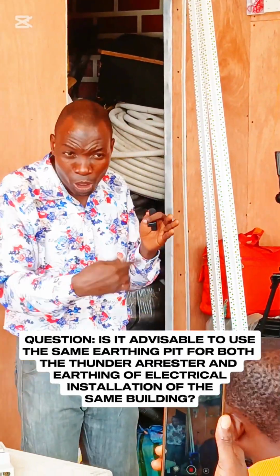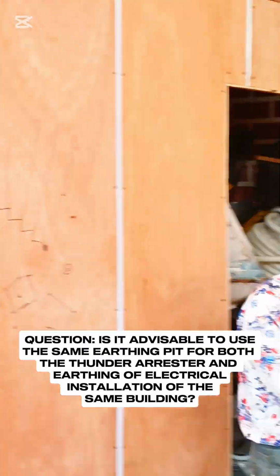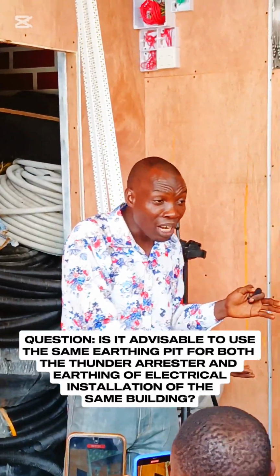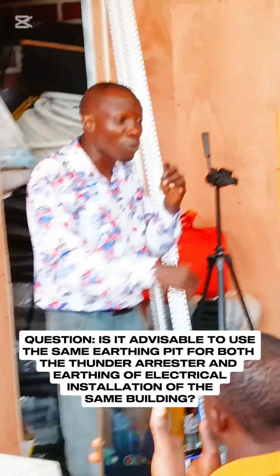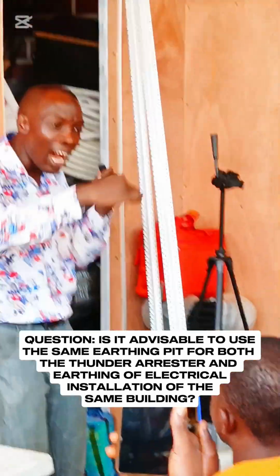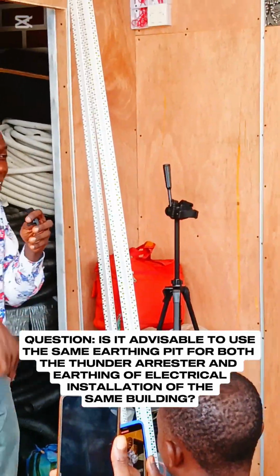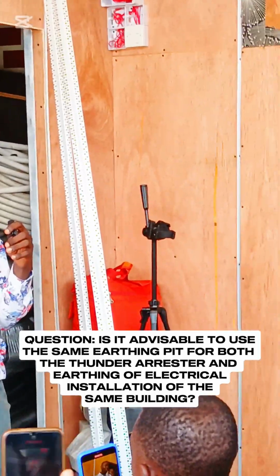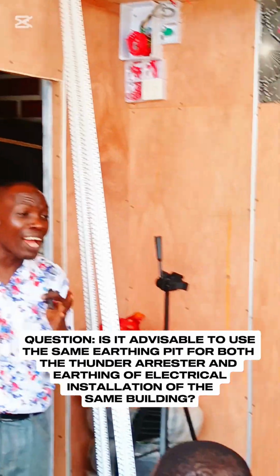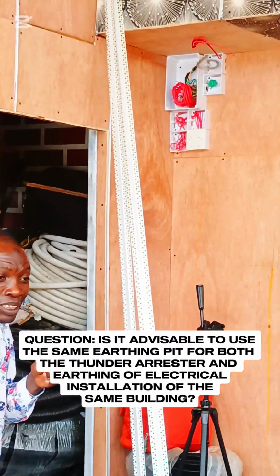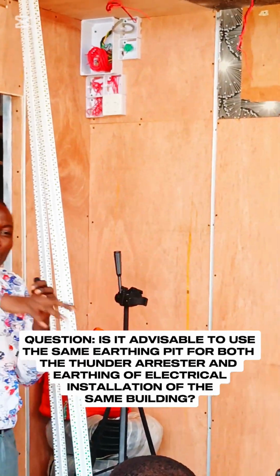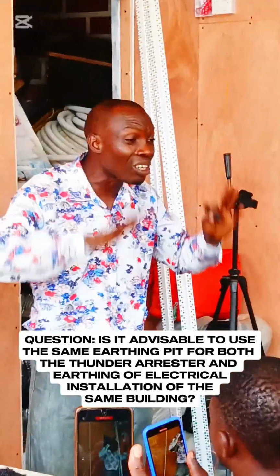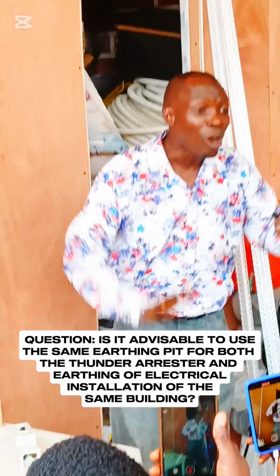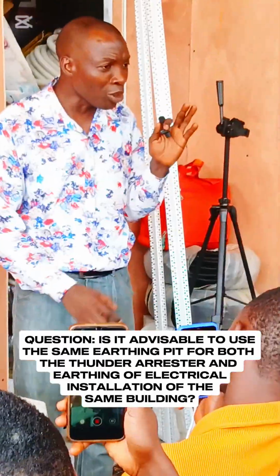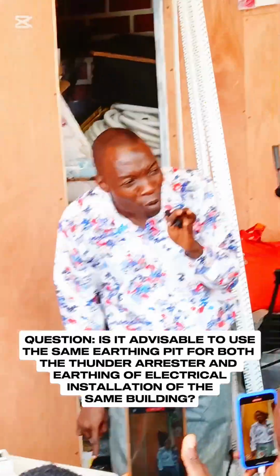Grounding it, remember we still had charcoal, industrial salt, animal dung, and so on. The essence of those things is to reduce the resistance of the earth. When fault current is flowing away and wants to enter the ground, the ground also has its own resistance, and current does not flow through a high resistance path. That is why you had industrial salt, that's why you had charcoal. All those components help to increase the conductivity of your ground, of your soil, so that when current is flowing, it can easily flow away.